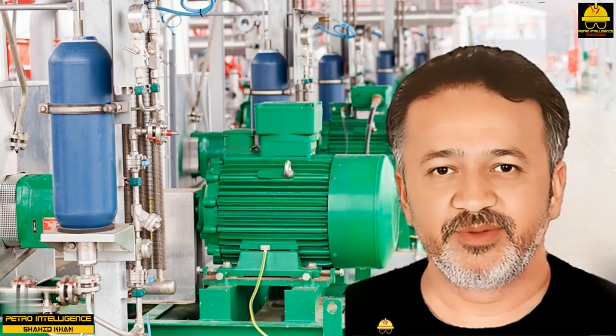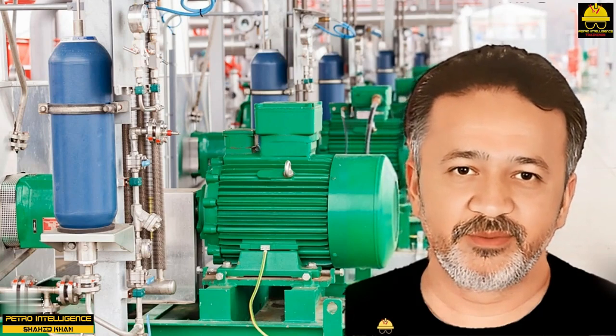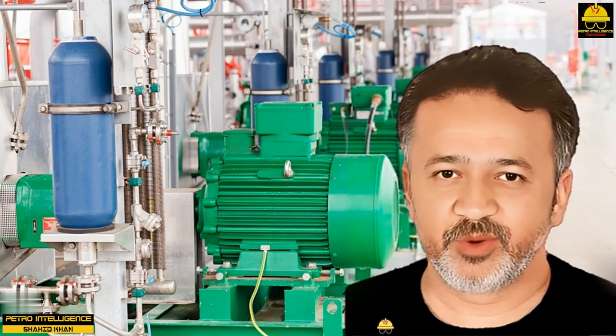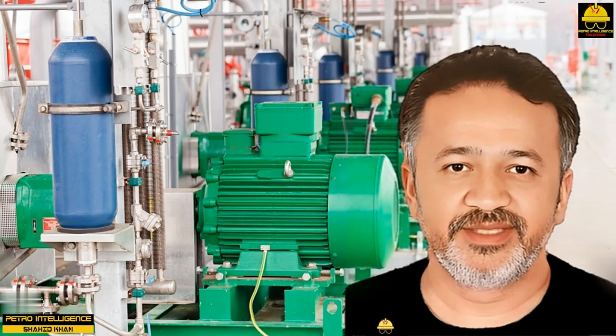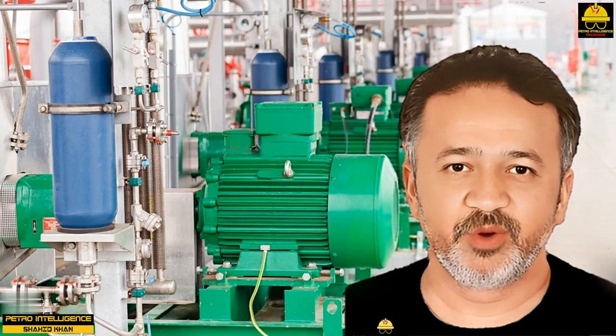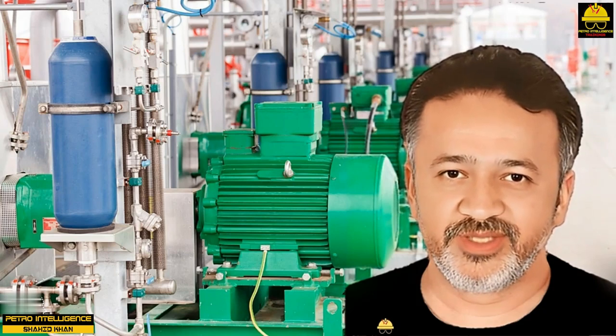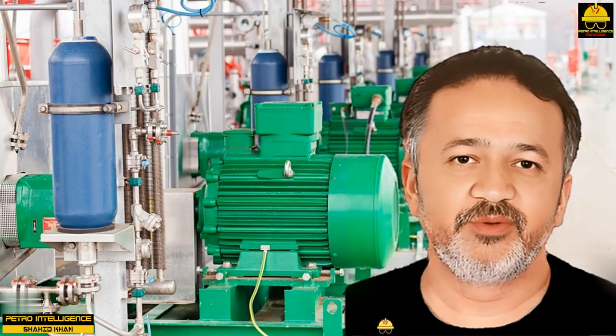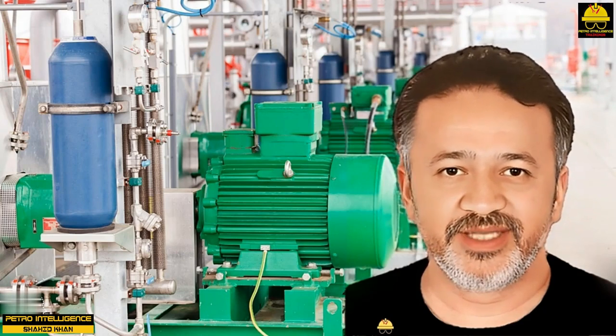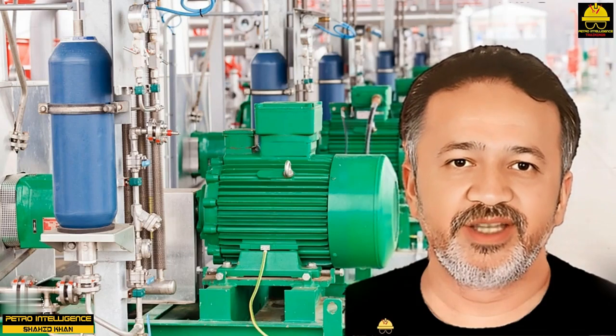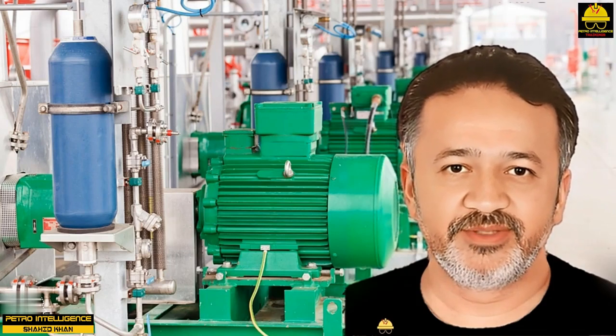Internal slip is the percentage of fluid that leaks or slips past the internal clearances of a pump over a given time. Centrifugal pumps can operate with 100% slip over short periods of time, discharge valve closed. Positive displacement pumps are not designed to tolerate slip, discharge valve closed.